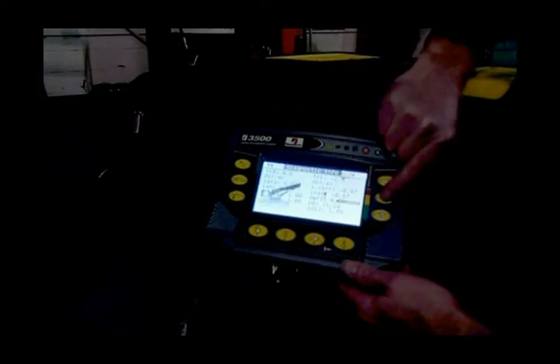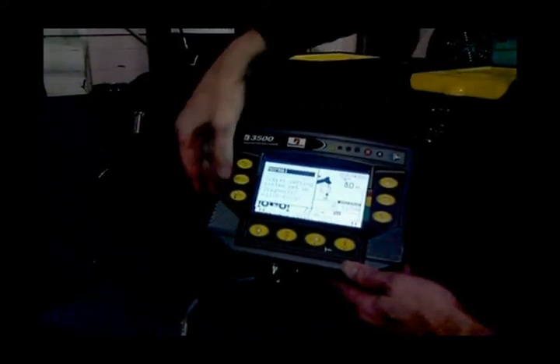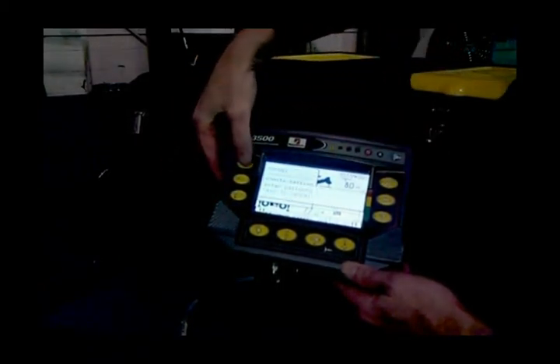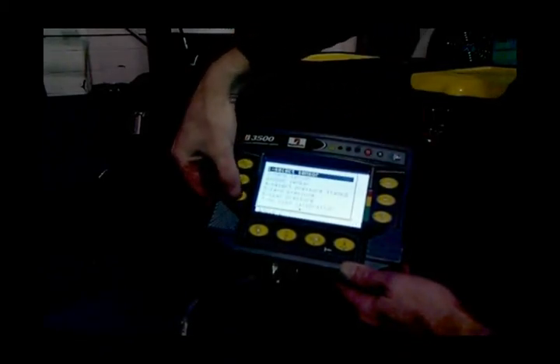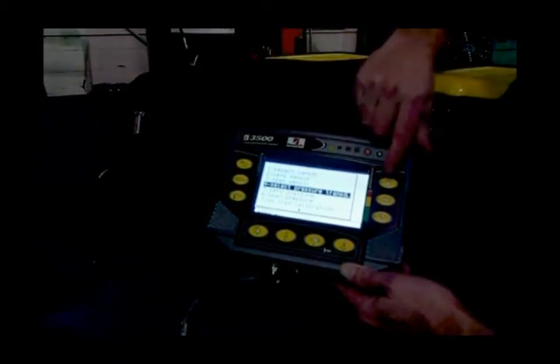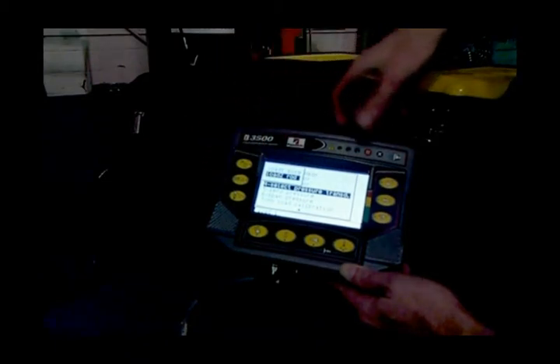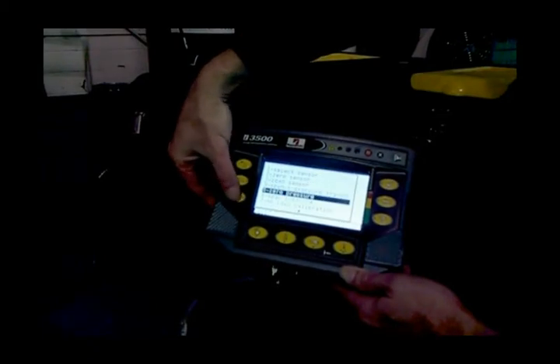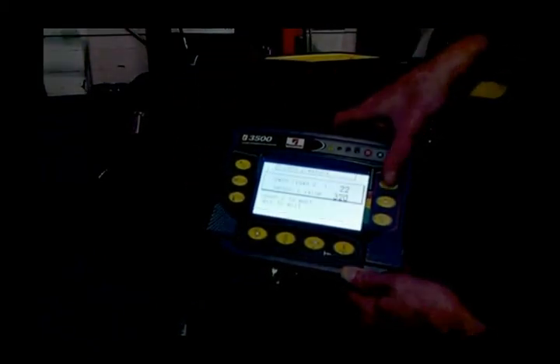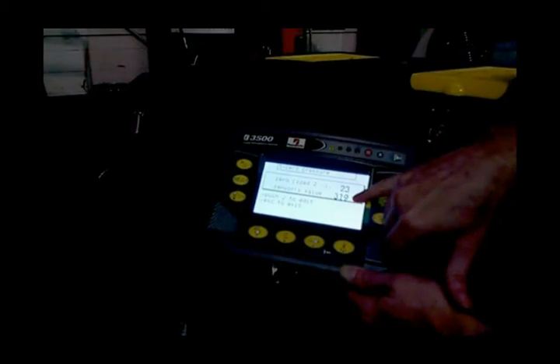All right, so we're going to go ahead and calibrate the rod side now. So we're going to hit the escape button. We're going to hit the mode, drop back down to calibration, hit the check mark, and enter the password. 1, 2, 3, 4. And we're going to scroll down to select pressure transducer. Hit the check mark, highlight load 2, which is the rod side, and hit the check mark.